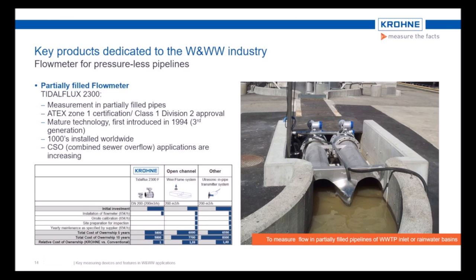Comparing this flow meter with the competitive ones, we see the EMF is unique on the market, only to be comparable with different measuring principles such as special weir or flume systems or ultrasonic in-pipe transmitter systems. Those might be a little more price attractive within the initial purchasing, however, they need to be calibrated on site and as well inspected and maintained yearly by the operator. So this is not required for the tidal flux EMF, which comes pre-calibrated and only needs to be plugged and then it plays. So comparing the costs over a certain period, we see clear benefits with the tidal flux mag meter.